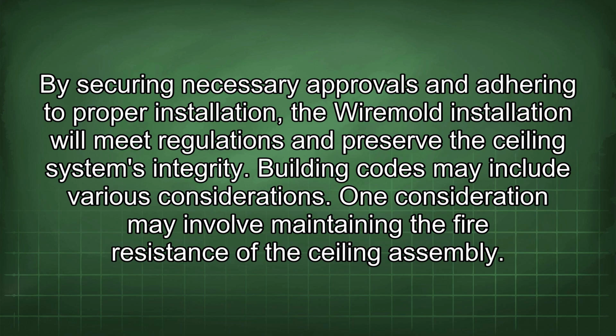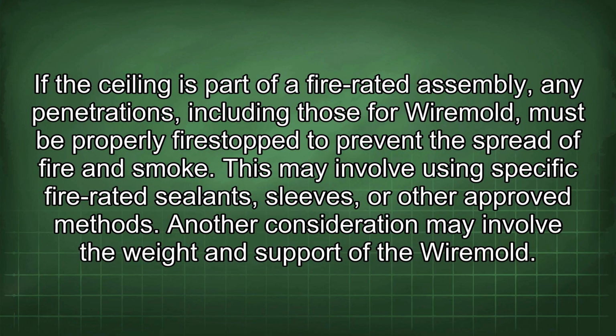By securing necessary approvals and adhering to proper installation, the Wiremold installation will meet regulations and preserve the ceiling system's integrity. Building codes may include various considerations. One consideration may involve maintaining the fire resistance of the ceiling assembly. If the ceiling is part of a fire-rated assembly, any penetrations, including those for Wiremold, must be properly fire-stopped to prevent the spread of fire and smoke. This may involve using specific fire-rated sealants, sleeves, or other approved methods.